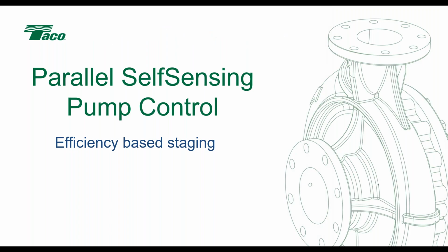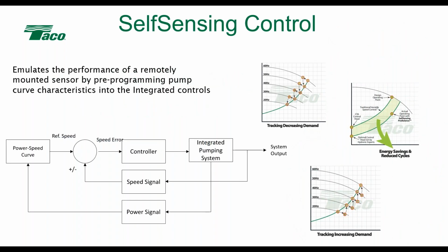So we look at this. How do we get the best efficiency out of all this? What we have to understand is that self-sensing, all the things that happen within self-sensing, all of that is contained within the drive and its component parts. So the power speed curve is loaded in there. All of the parameters for the motor are loaded in there, and everything works as an integrated system. So you've got the pump, the motor, the drive, everything is all contained in one system.